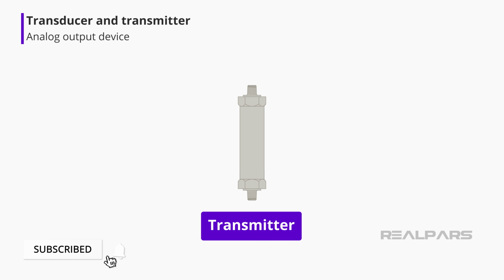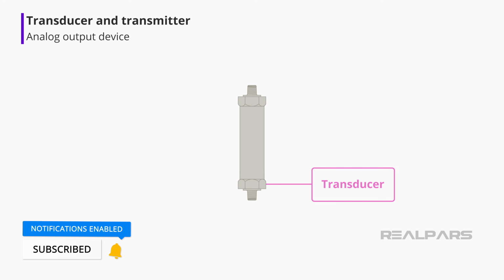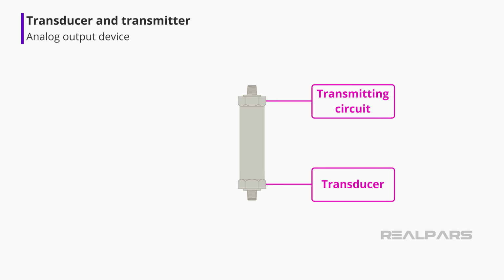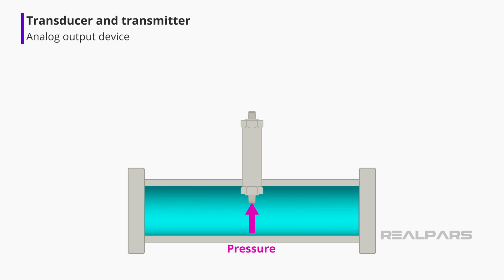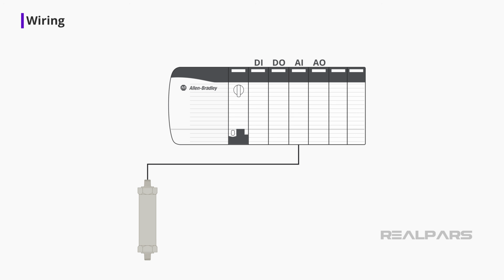A pressure transmitter is a two-part device consisting of a sensing transducer and a circuit that transmits a standard instrumentation electrical signal representing a physical variable being measured. In most applications, the electrical signal is 4 to 20 milliamps. A pressure transmitter is an analog device and is therefore connected to a PLC analog input module. Many people refer to this device as a transducer. For the sake of simplicity, we'll continue to refer to it as a transmitter.